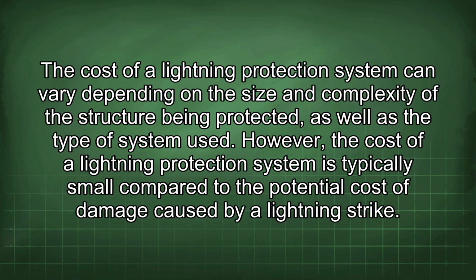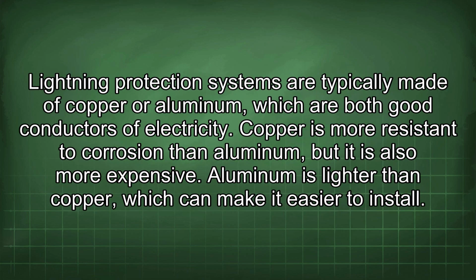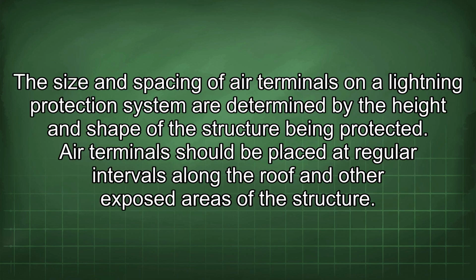Lightning protection systems are typically made of copper or aluminum, which are both good conductors of electricity. Copper is more resistant to corrosion than aluminum, but it is also more expensive. Aluminum is lighter than copper, which can make it easier to install. The size and spacing of air terminals on a lightning protection system are determined by the height and shape of the structure being protected.